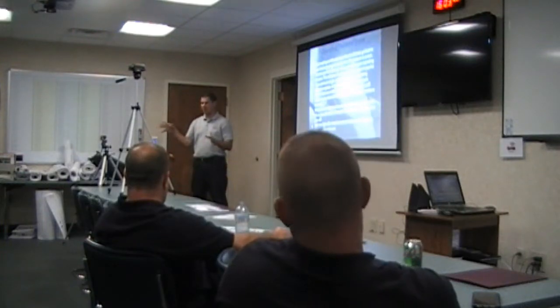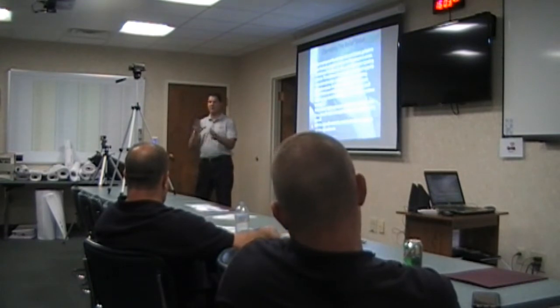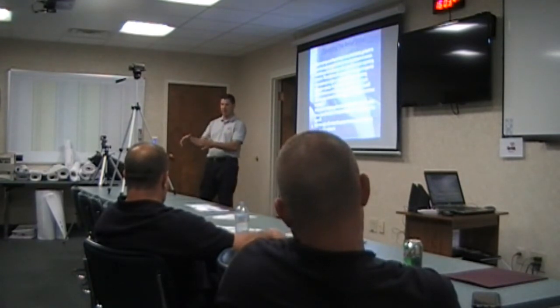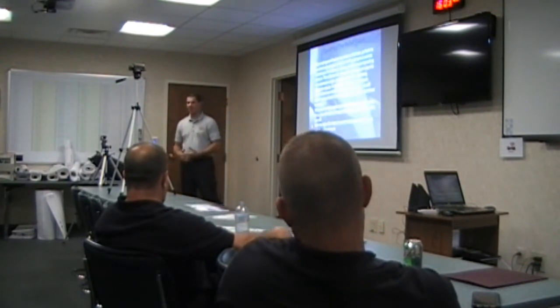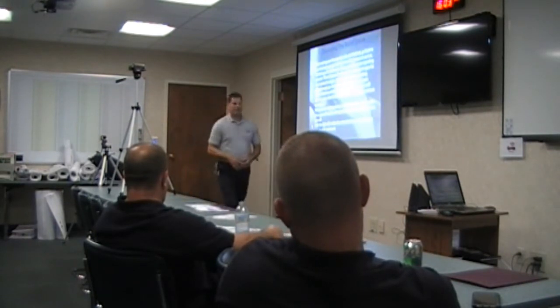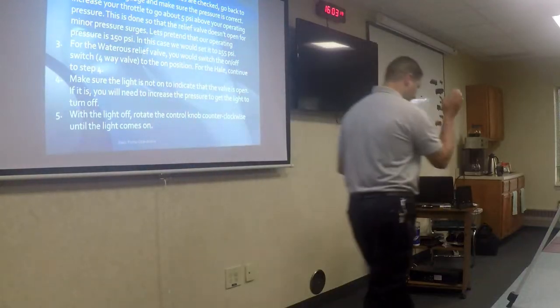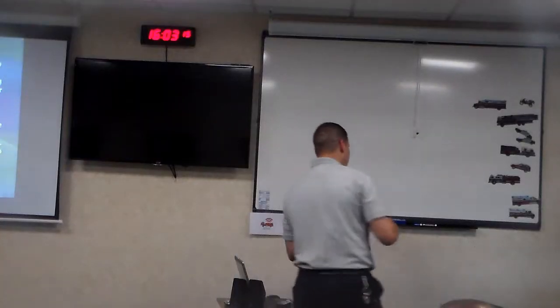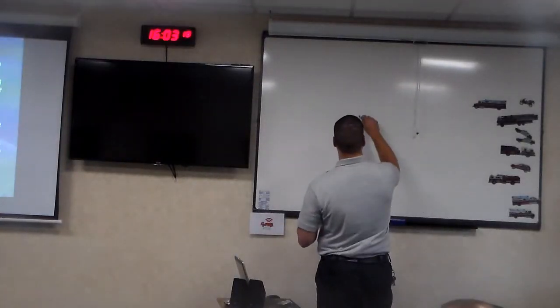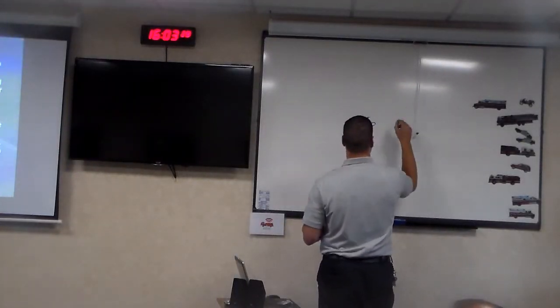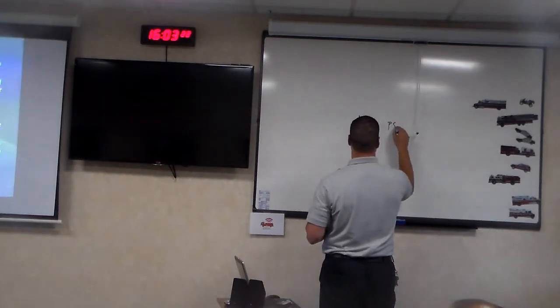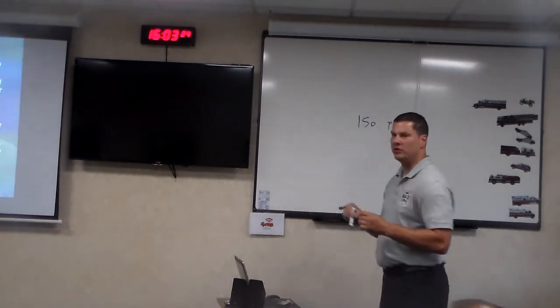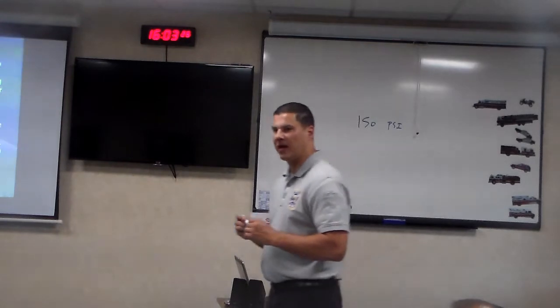We have to be at our operating pressure, correct? Whatever we set the discharge valve to has to be done, and then we can go ahead and set the relief valve. If, through whatever math we use in our charts, we come up with a discharge pressure of 150, that's what we set our gauge to. Now we're ready to do the relief valve.